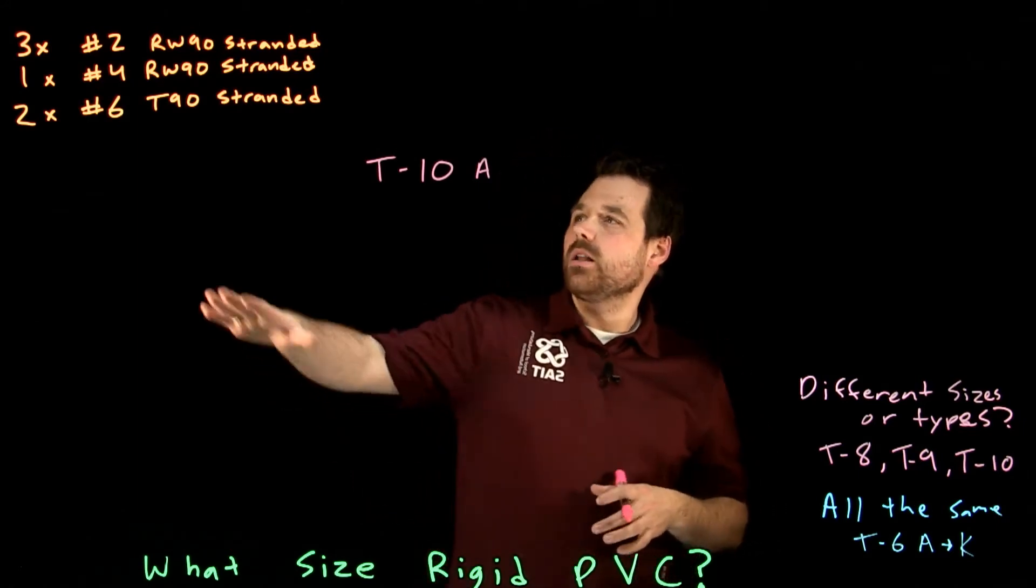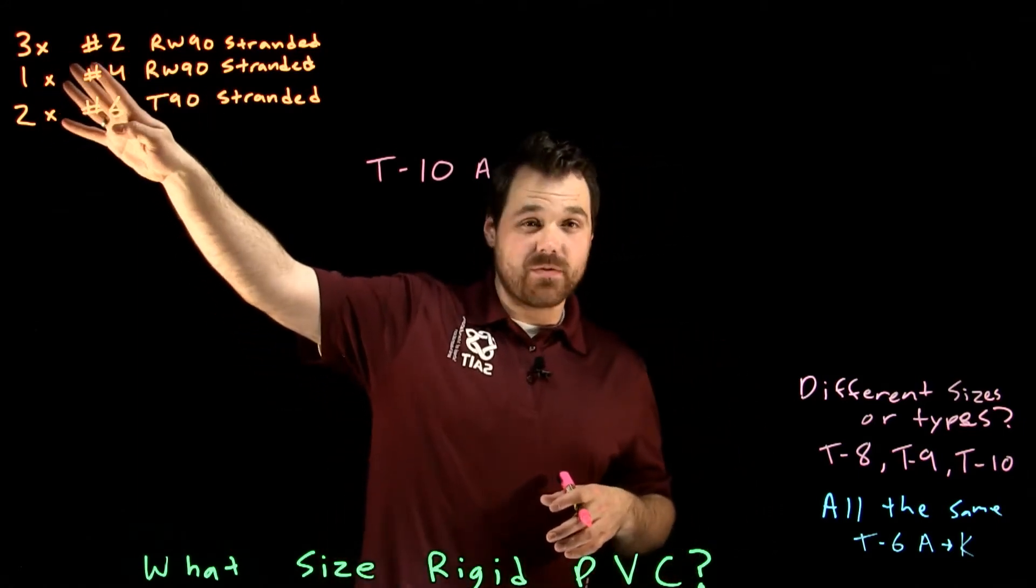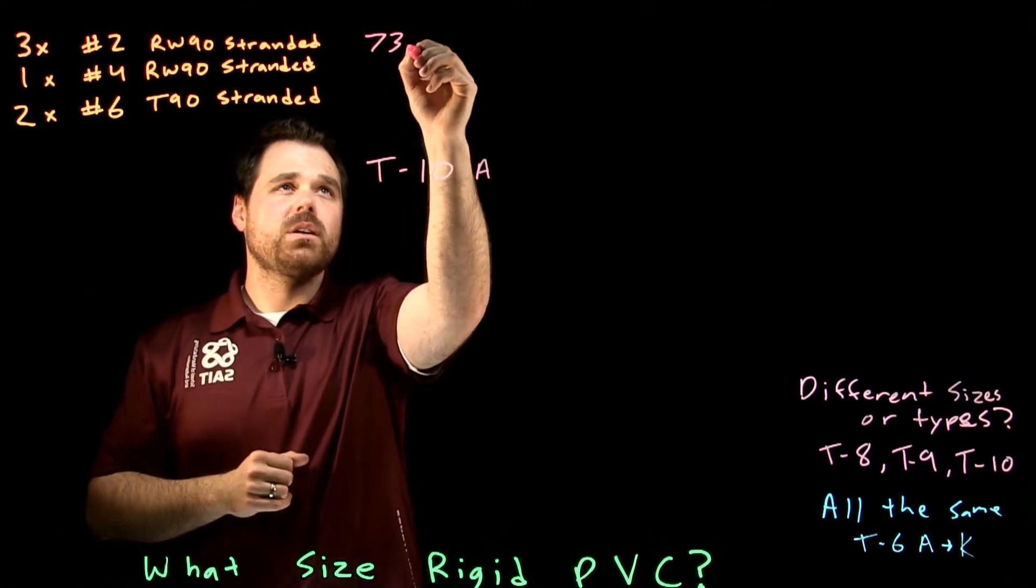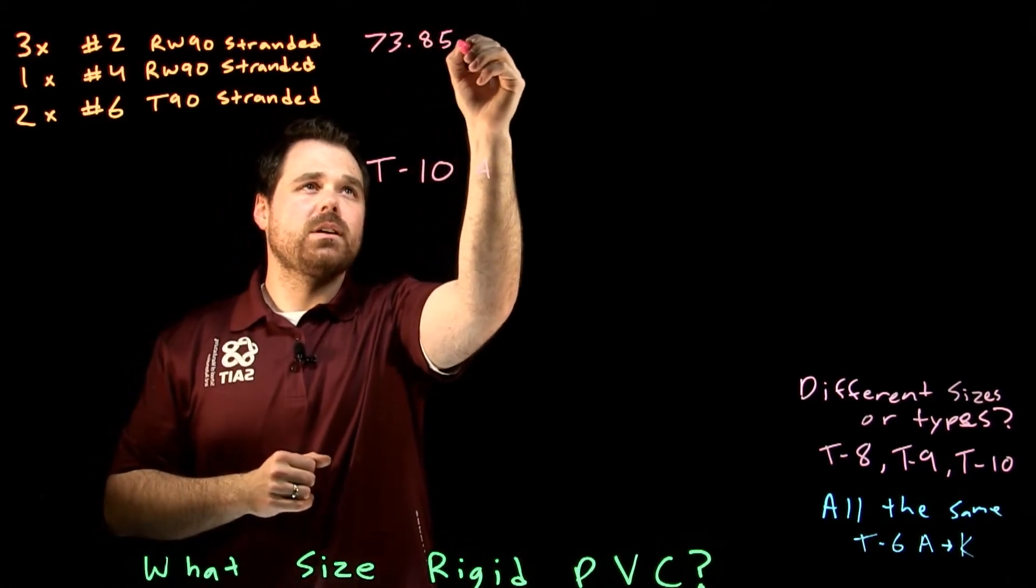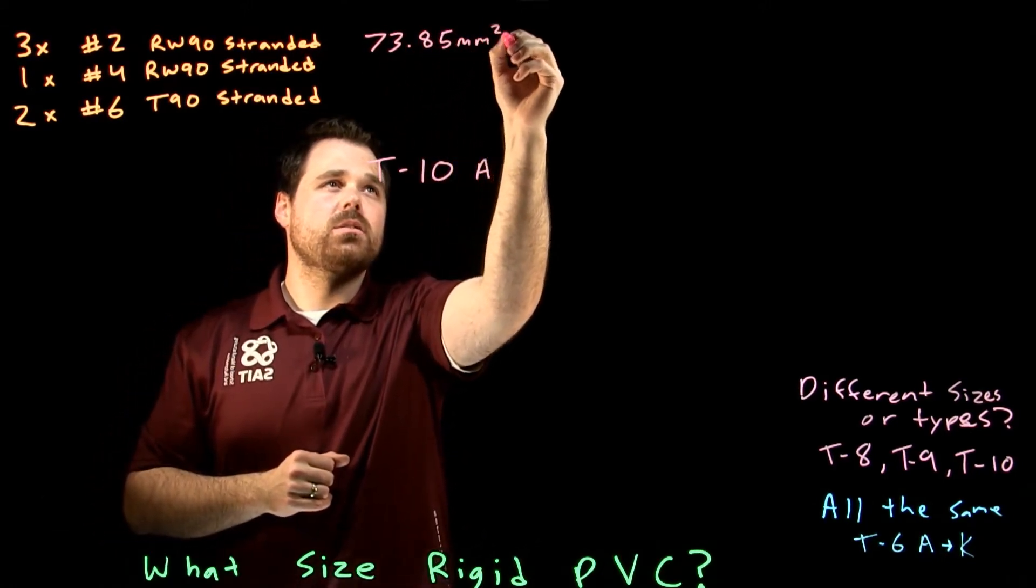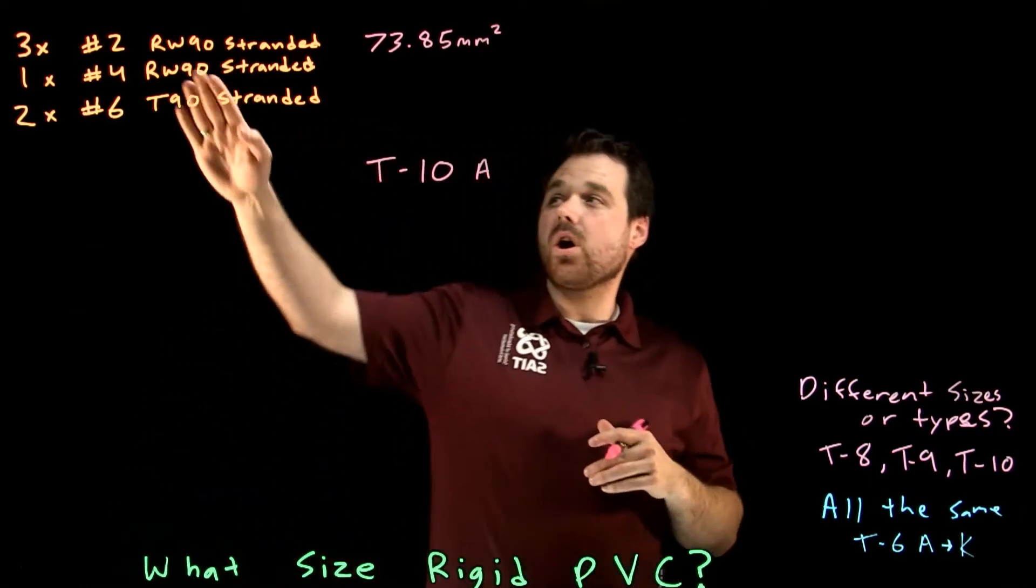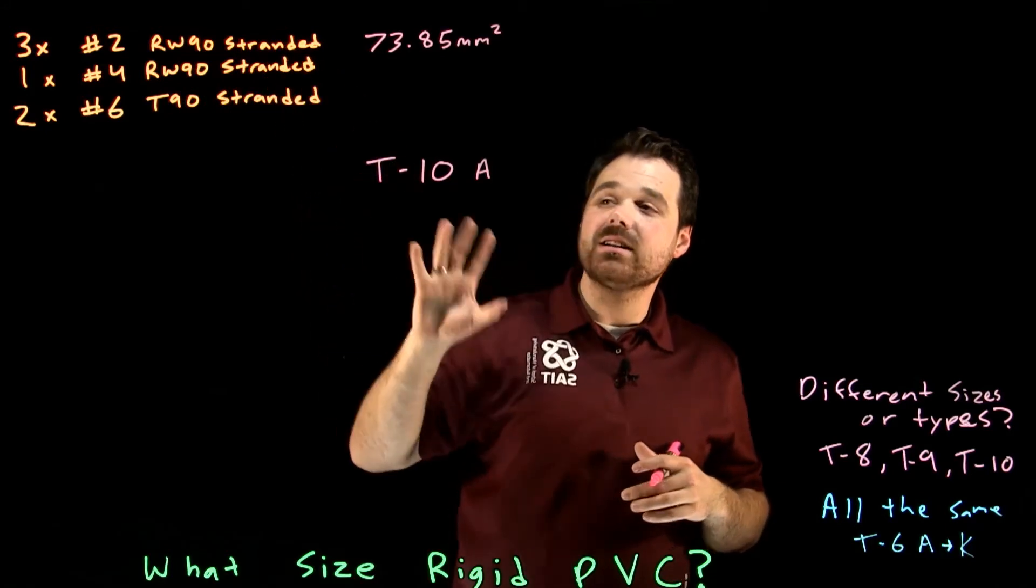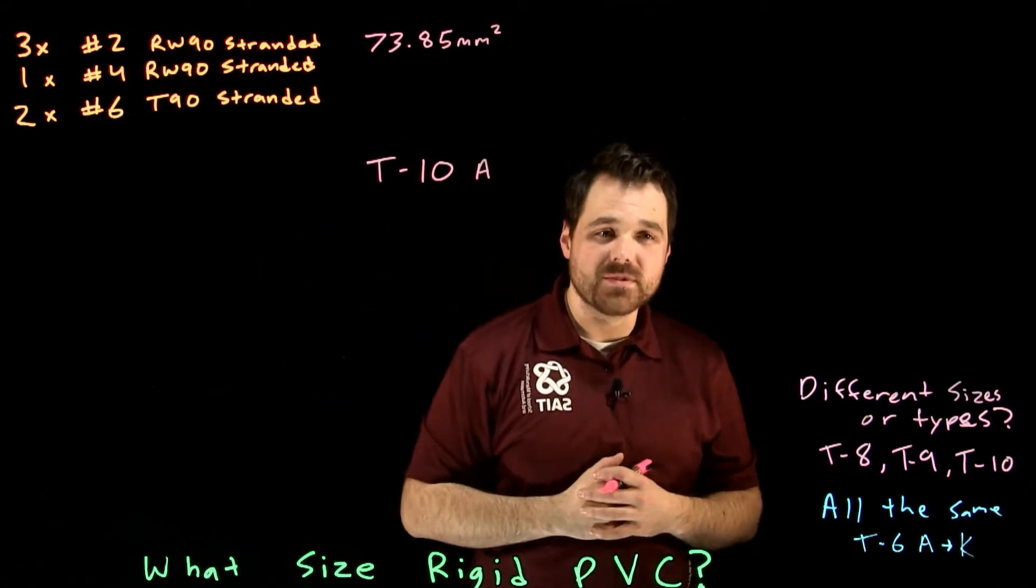Table ten A is going to tell us the area or the millimeter squared for each conductor. So this is the way I like to lay it out. I like to take my number twos, yes we have three of them, but I like to go to table ten and I like to say each number two is actually good for seventy three point eight five millimeters squared. I like to get that number. That is the circular area of one RW90 stranded number two conductor from table ten A.